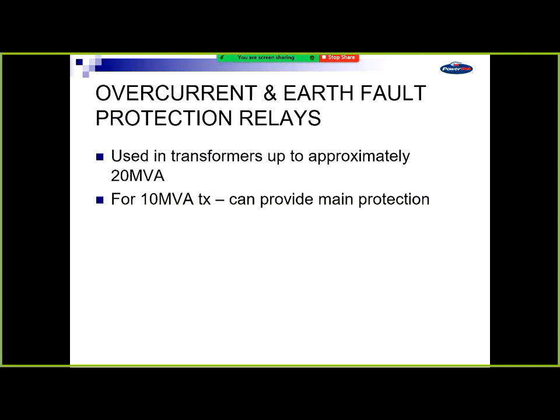As I said earlier, we've got bias diff and we use that one panel of bias diff. Doesn't matter whether it's a 500 MVA transformer or a 20 MVA transformer. It's just quicker for us to go, that's what we've got, put it in there. This is the standard design. We save a lot of time on that.